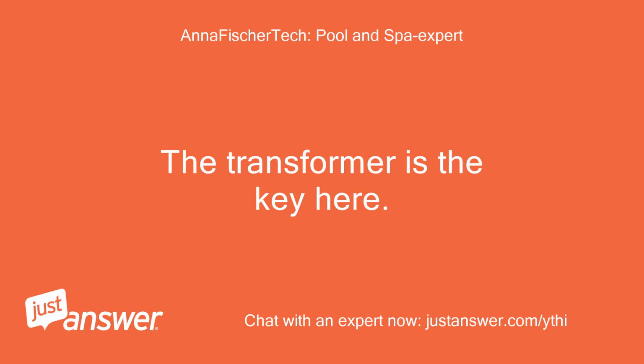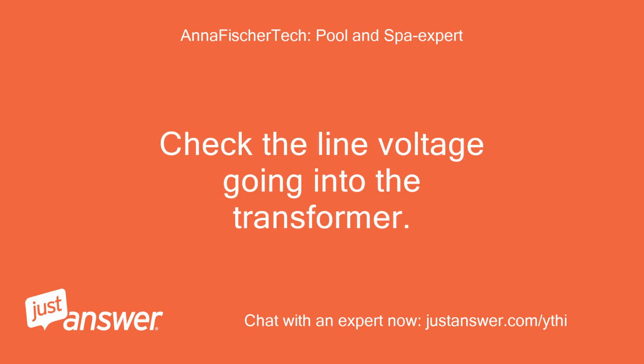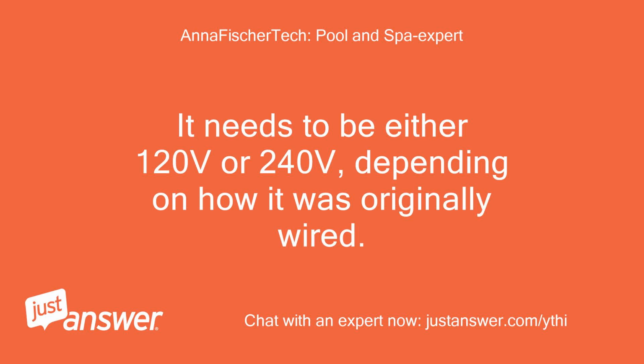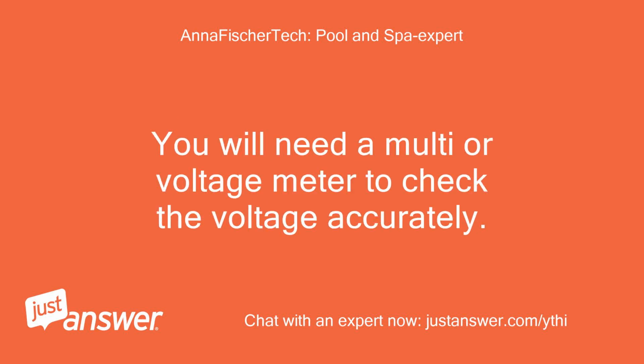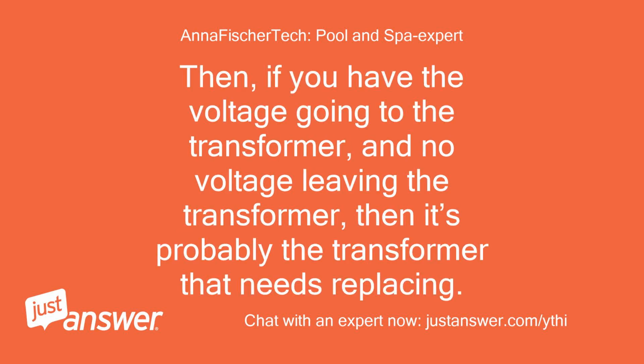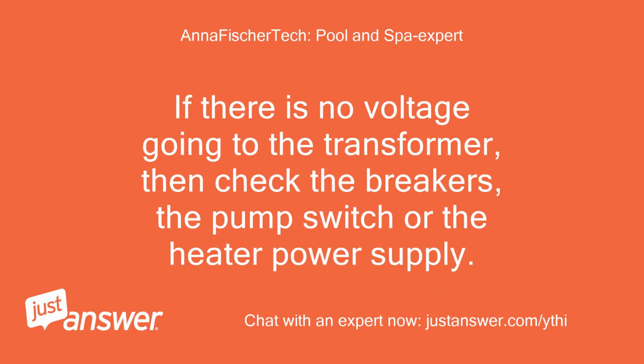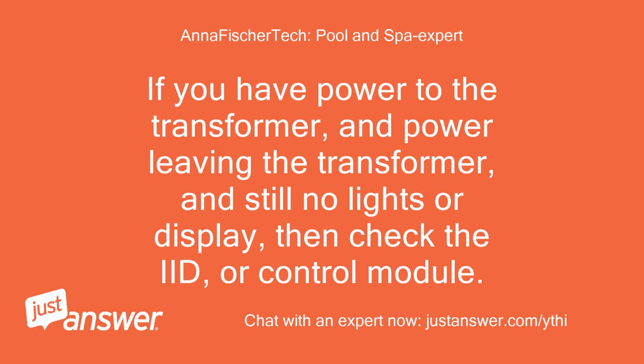The transformer is the key here. Check the line voltage going into the transformer. It needs to be either 120 volts or 240 volts, depending on how it was originally wired. You will need a multimeter or voltage meter to check the voltage accurately. Then, if you have the voltage going to the transformer and no voltage leaving the transformer, then it's probably the transformer that needs replacing. If there is no voltage going to the transformer, then check the breakers, the pump switch or the heater power supply. If you have power to the transformer and power leaving the transformer and still no lights or display, then check the IID or control module.